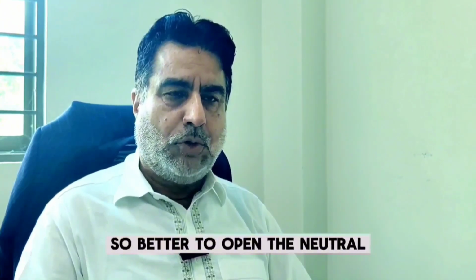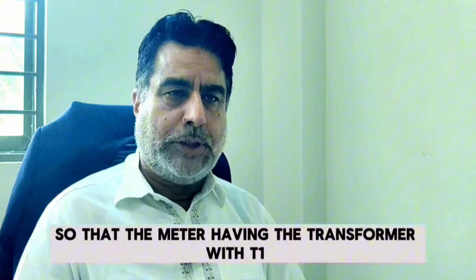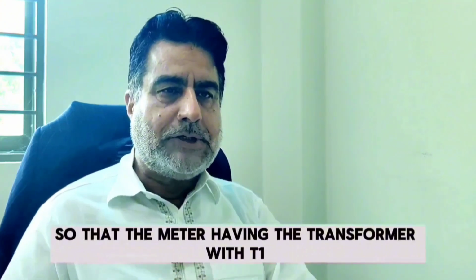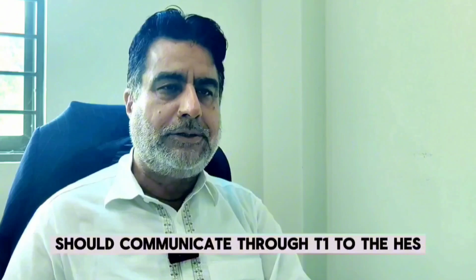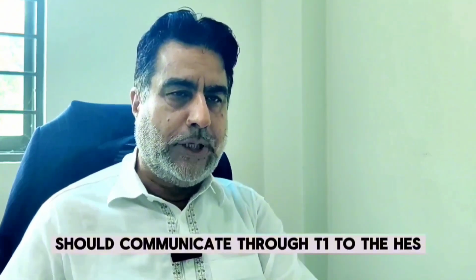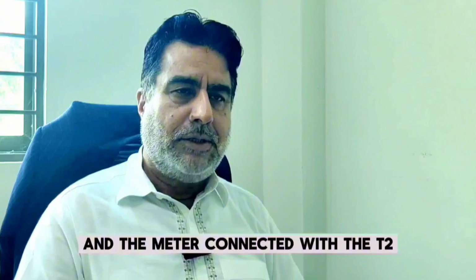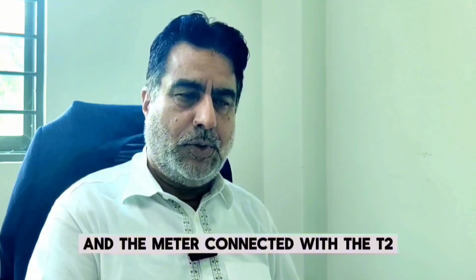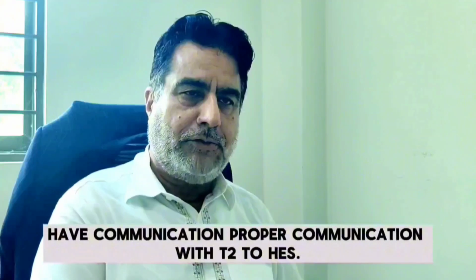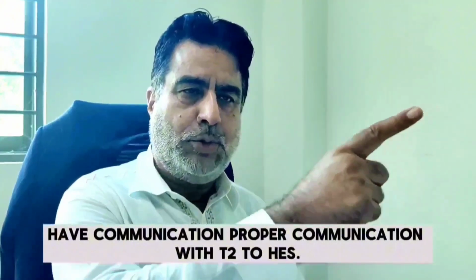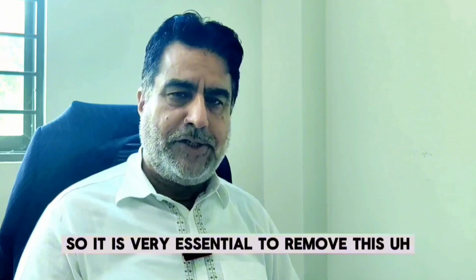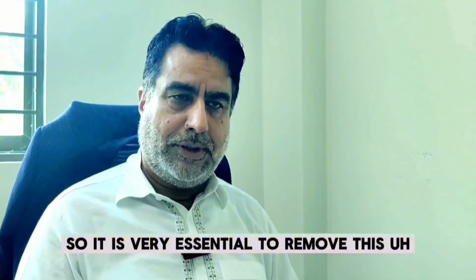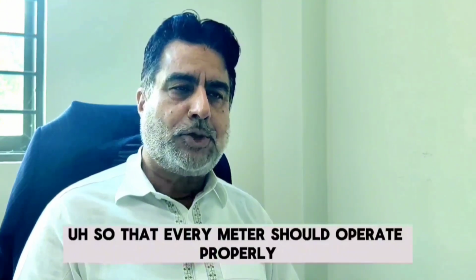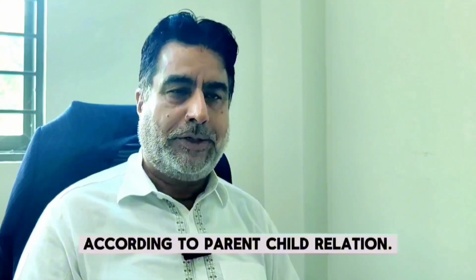So it is better to open the neutral so that the meter connected with transformer T1 communicates through T1 to the HES, and the meter connected with T2 has proper communication with the HES through T2. So it is very essential to remove this common neutral so that every meter operates properly according to the parent-child relation.